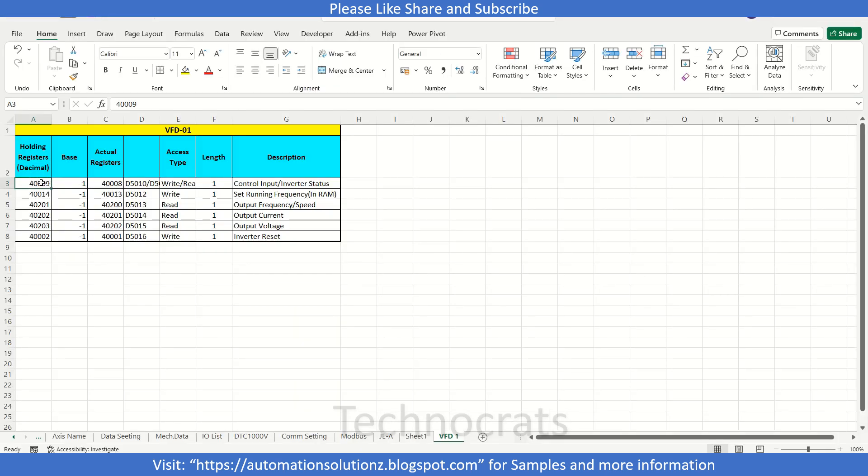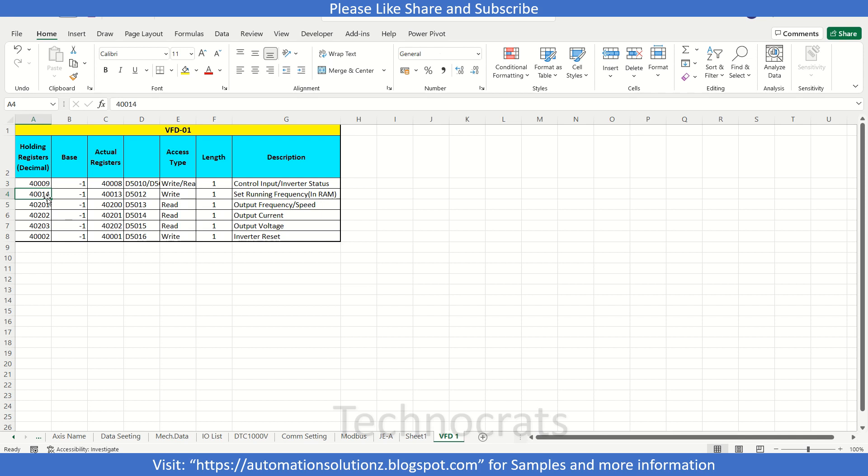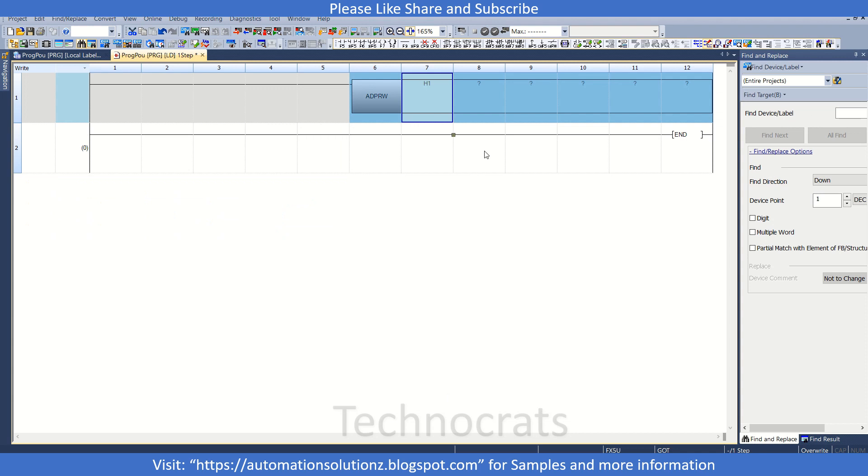Now all the addresses are shown here in the left side. I will maintain the Excel so we can use this Excel to get the address. To set the frequency we have to use the holding register 40014. So we will reduce it by one because our base is minus one, and the actual register which we will write data to is 40013.